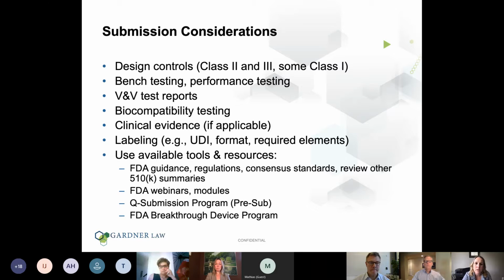So if you have questions about your submission, regulatory questions about the strategy, or questions about the clinical study, FDA does encourage you to use the pre-sub program. A lot of people shy away from that just because it's another few months added into the timeline. But really, I've seen that it actually results in time savings in a lot of cases. If you go in to the FDA with a submission where maybe they don't agree with the clinical testing or the testing strategy, you would end up losing time during that process. So it is something that you should consider and maybe use as appropriate.